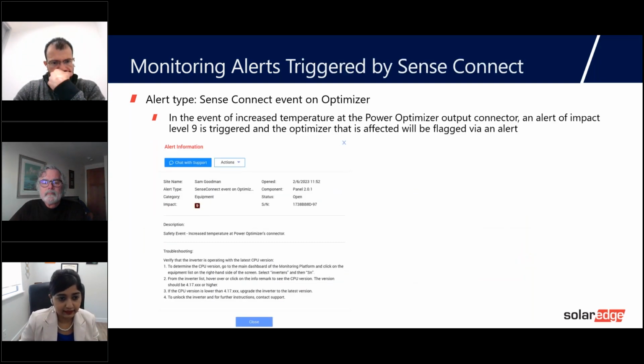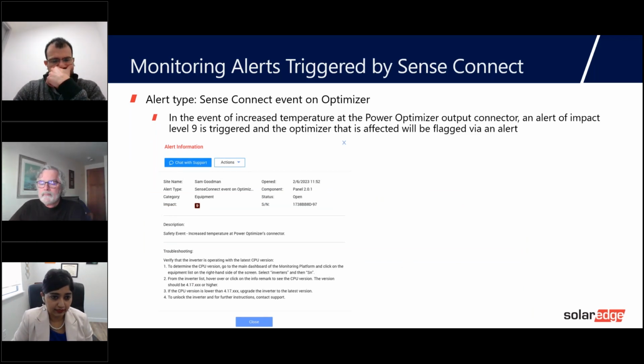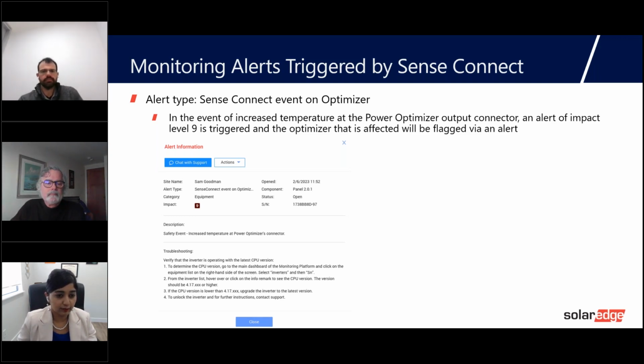Next slide, please. So yeah, here's an example of an alert that is generated by a SenseConnect event triggered on an optimizer. So this is where, in the event of an increased temperature at the power optimizer output connector, an alert of impact level 9 was triggered, and the panel that is affected will be flagged via an alert that looks like the screenshot on this slide. And as you can see, the alert also provides some specific troubleshooting tips. So you can figure out which specific panel was affected. Next slide, please.